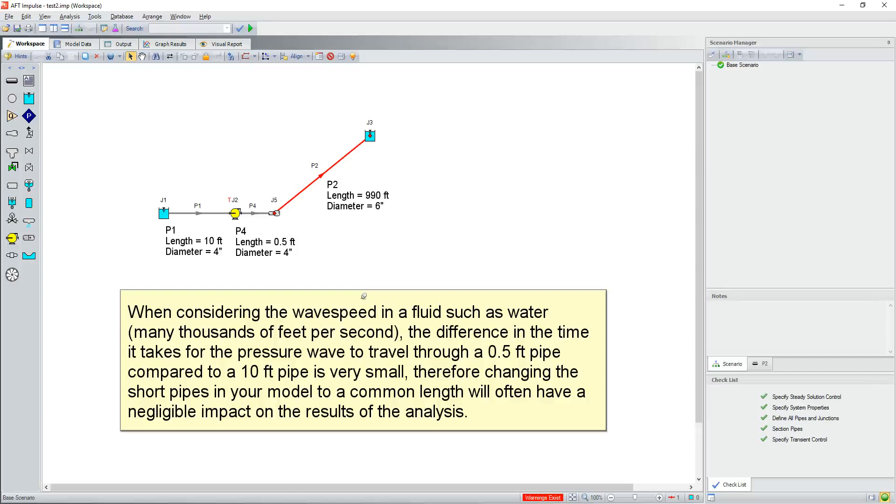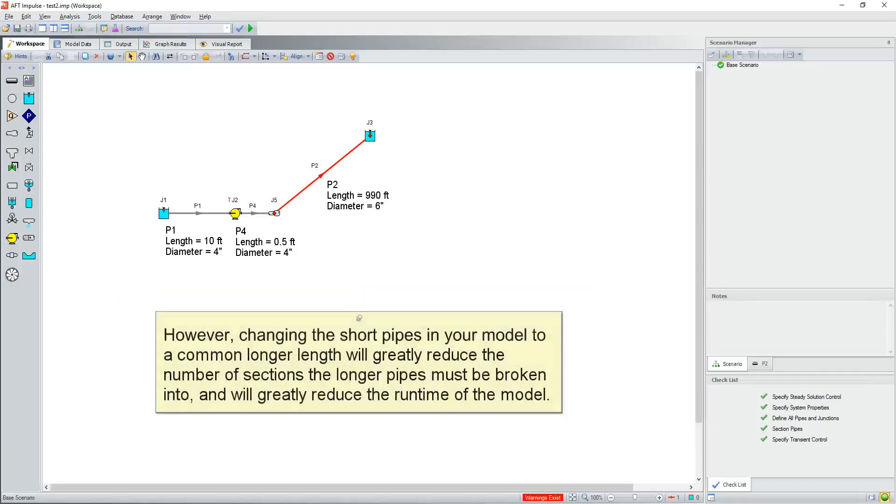However, changing the short pipes in your model to a common longer length will greatly reduce the number of sections the longer pipes must be broken into and will greatly reduce the runtime of the model. There is an exponential relationship between runtime and the number of sections in the model.